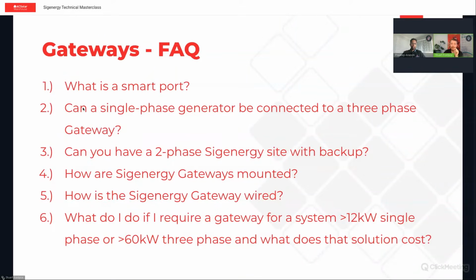Now, part of this is that we often get asked, can the Sigenergy energy controllers control third-party solar systems via frequency control? And the answer is yes. You do have to stick to a 1-to-1 ratio currently. That's what the Sigenergy manual will dictate. And that means if you've got a 10 kilowatt energy controller, a single phase gateway, you can have no bigger than 10 kilowatts of a third-party solar system coming through that smart port.